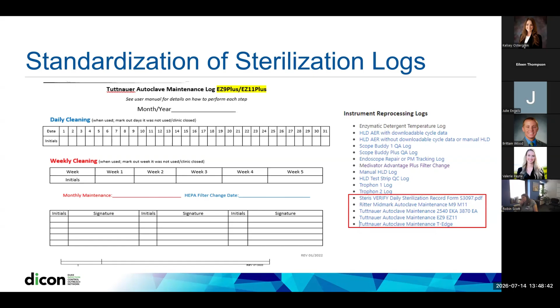But not only is documentation of the sterilization important, but so is maintenance of our autoclaves. Here's just a sample log of autoclave maintenance for one of the manufacturers used within one of the practices. This particular IFU has specifics for daily, weekly, and monthly maintenance. A nice component of this log is on the back. The previous IPs had gone to those IFUs and clearly outlined what should be performed daily, weekly, monthly, etc. So that was a really nice quick reference cheat sheet for staff.